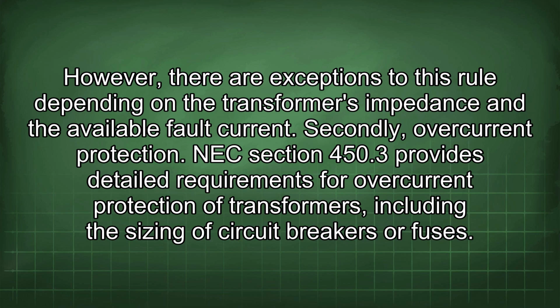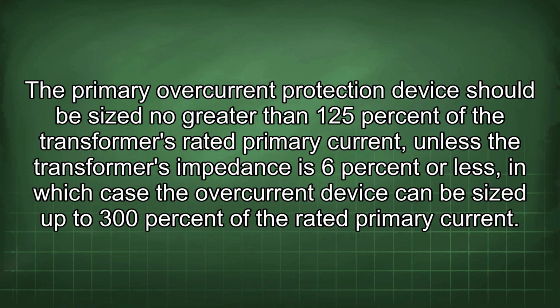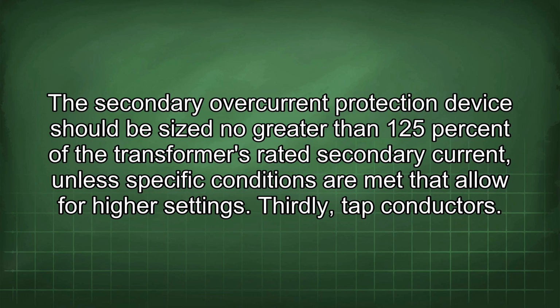Secondly, overcurrent protection. NEC Section 450.3 provides detailed requirements for overcurrent protection of transformers, including the sizing of circuit breakers or fuses. The primary overcurrent protection device should be sized no greater than 125% of the transformer's rated primary current, unless the transformer's impedance is 6% or less, in which case the overcurrent device can be sized up to 300% of the rated primary current. The secondary overcurrent protection device should be sized no greater than 125% of the transformer's rated secondary current, unless specific conditions are met that allow for higher settings.